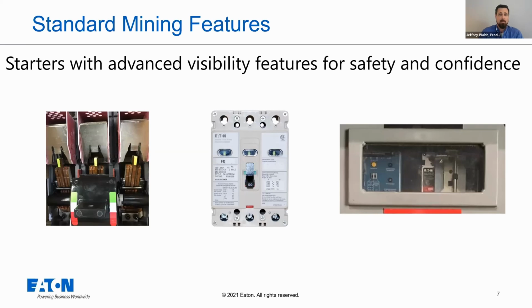And then we add windows to the faceplate of the breaker. So when you combine this with our enclosure, you have a window that you can see through the enclosure, and through visual confirmation you can confirm that the breaker is energized or de-energized. So it introduces another level of safety when someone can look through the enclosure and have an understanding, before lockout tagout, whether the unit is really de-energized. That extra awareness has been key, and a lot of people don't realize that feature is out there. And once they do realize it, it's very much a want in the industry.